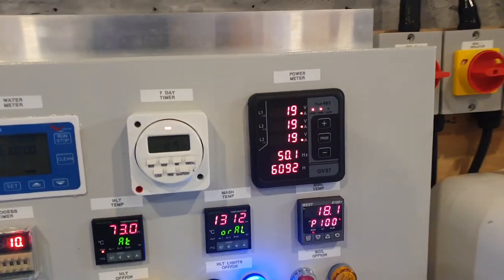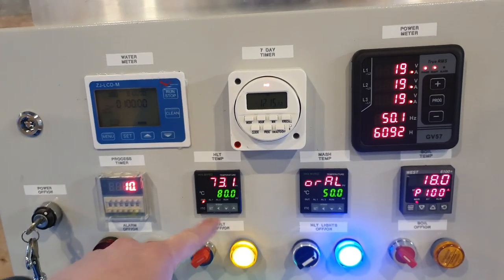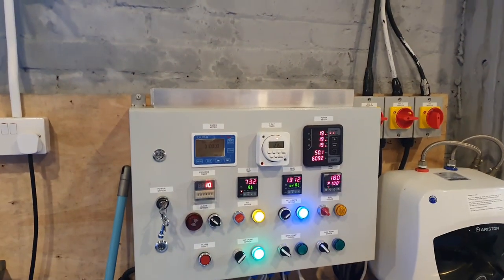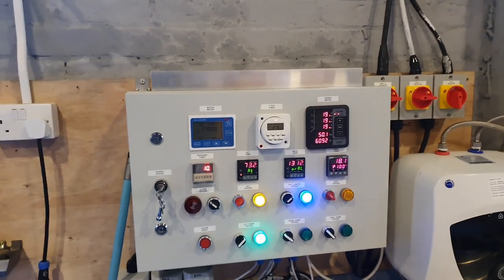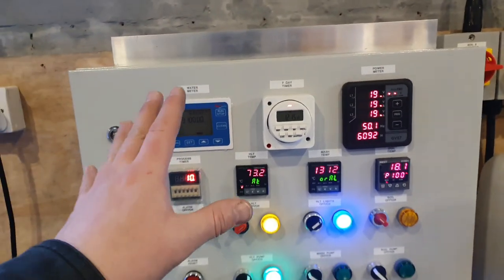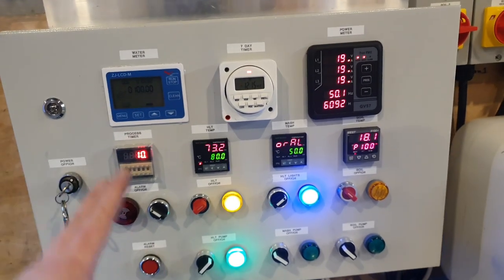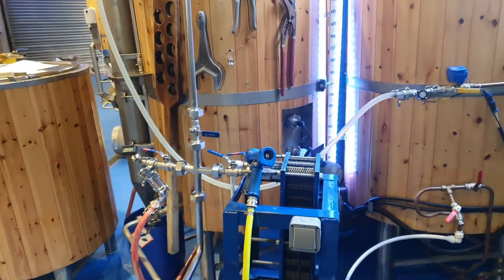The pump is on and everything looks stable - there don't seem to be any fluctuations on here at all or on here. That reading is climbing - I think we've cracked it. That feedback could have been what caused the solid state relay to fail in the first instance, so the fact that we've eliminated it is certainly not a bad thing.